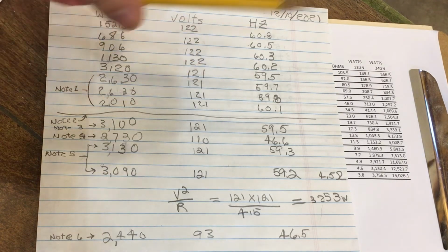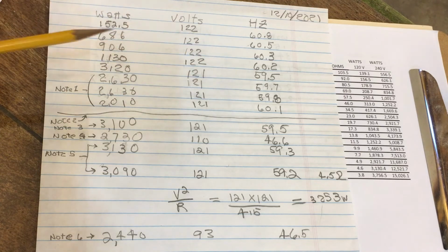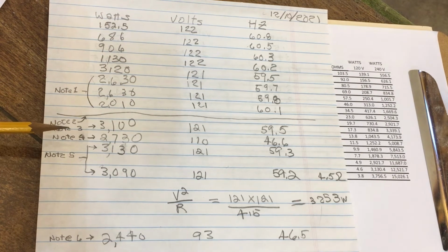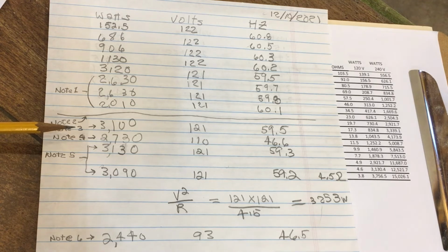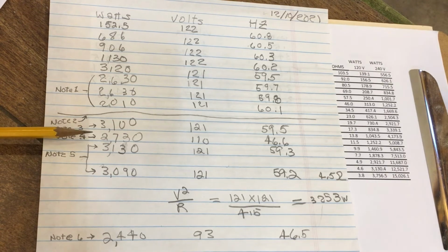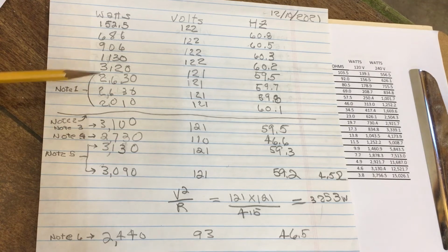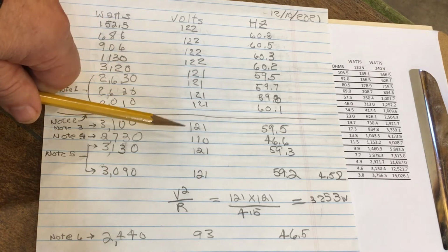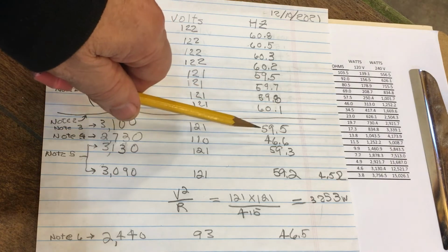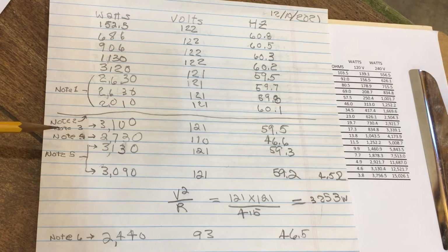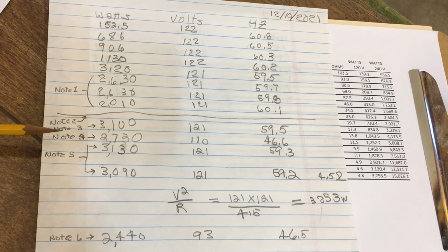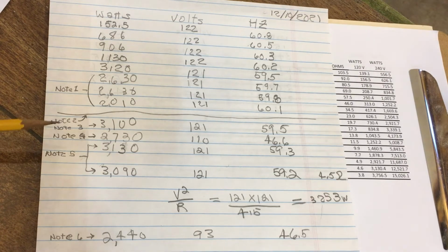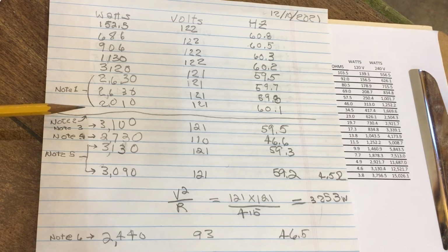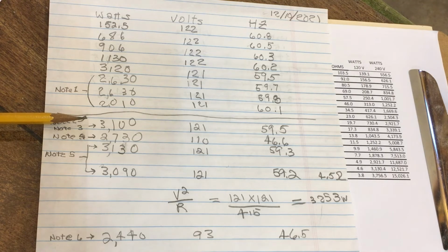Again, the voltage looked good. Frequency was quite reasonable. And then the next line, I increased the load some additional amount, and instead of increasing the load, it went down, similar to what happened up above. However, you'll notice that the voltage dropped to 110 and the frequency dropped to 46.6. The generator was going down on its knees. We had reached all it could do, and so I reset the switches back to the setting that we saw on line 1. This time I got a reading of 3130.